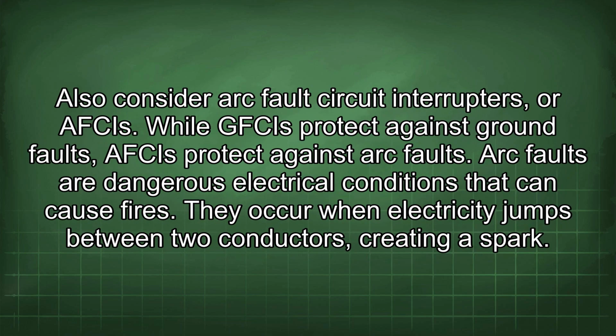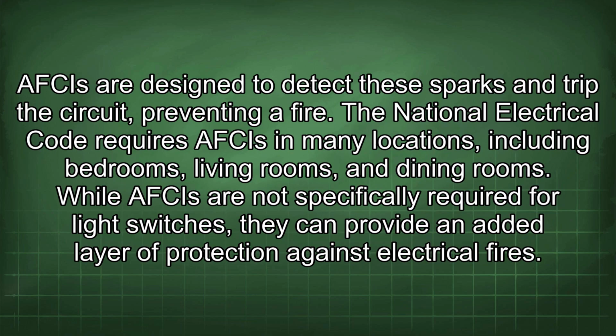Also consider arc fault circuit interrupters, or AFCIs. While GFCIs protect against ground faults, AFCIs protect against arc faults. Arc faults are dangerous electrical conditions that can cause fires. They occur when electricity jumps between two conductors, creating a spark. AFCIs are designed to detect these sparks and trip the circuit, preventing a fire. The National Electrical Code requires this protection in many locations, including bedrooms, living rooms, and dining rooms. While AFCIs are not specifically required for light switches, they can provide an added layer of protection against electrical fires.